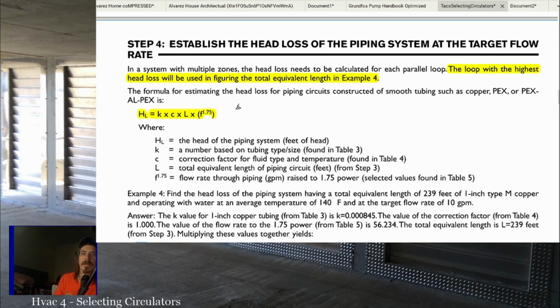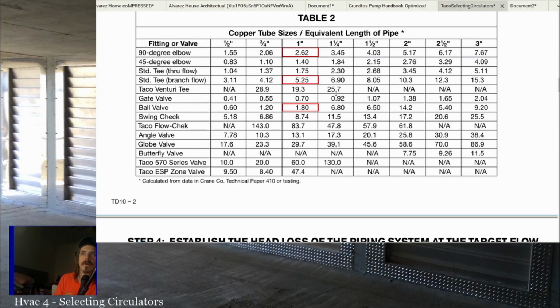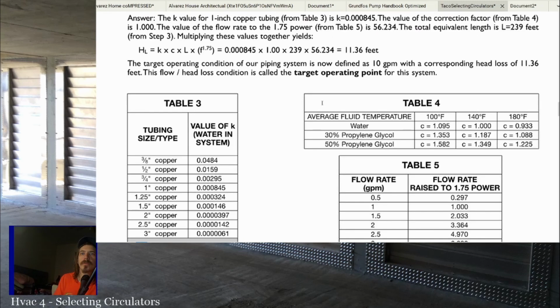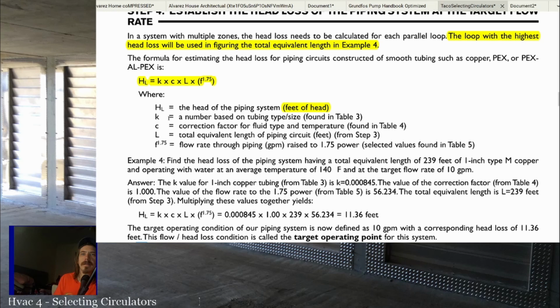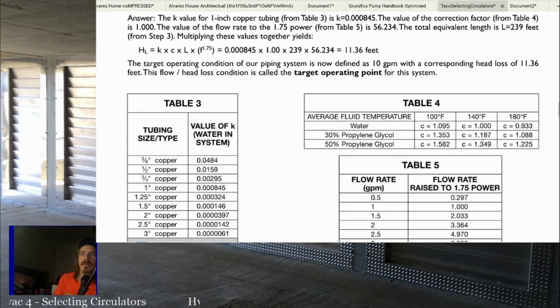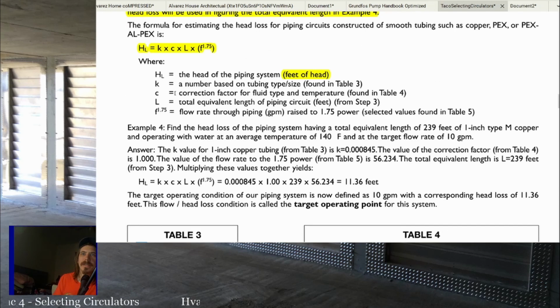So this is our formula. Head loss is what we're trying to find, in feet of head, because everything's in feet of head. K is a number based on the tubing size, so you have to find that in table 3 right here. K is just a constant based on your tubing size. C is a correction factor for the fluid type and temperature. That's just a constant for the temperature you're going to run at and the type of fluid you have. This is basically a density correction for the fluid. Different temperatures change the density of water.